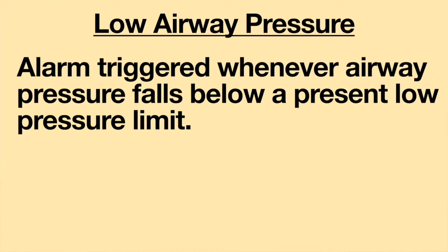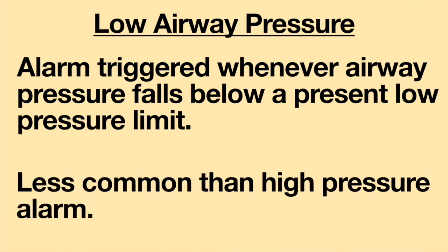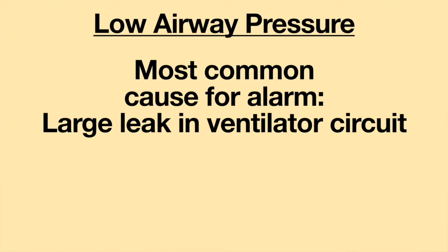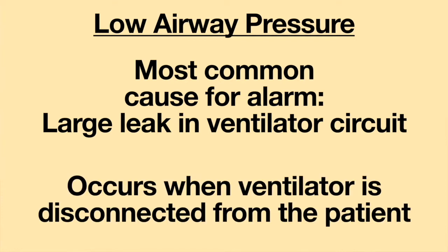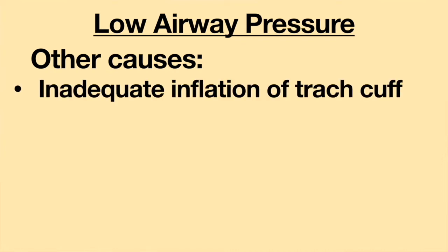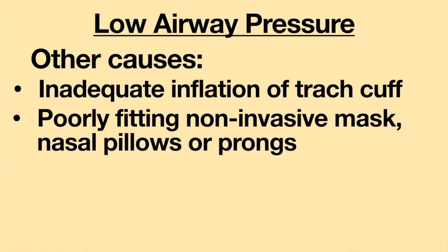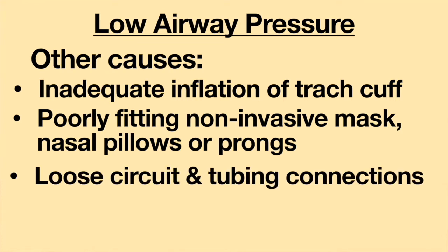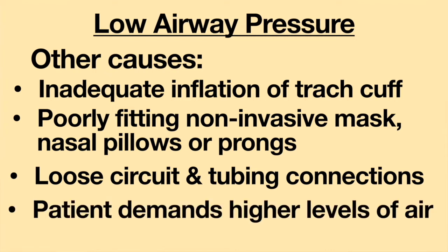A low airway pressure alarm is triggered whenever airway pressure falls below a preset low pressure limit. This is much less common than a high pressure alarm. This often occurs when there is a large leak in the ventilator circuit, most often when the ventilator circuit becomes disconnected from the endotracheal or tracheostomy tube. Other causes include inadequate inflation of the tracheostomy tube cuff, a poor-fitting non-invasive mask, nasal pillows or prongs, loose circuit and tubing connections, and the patient demanding higher levels of air than the ventilator is putting out.